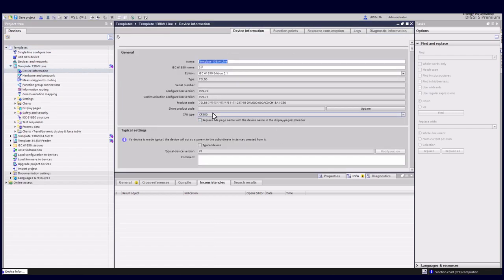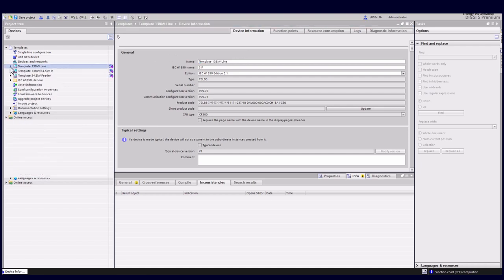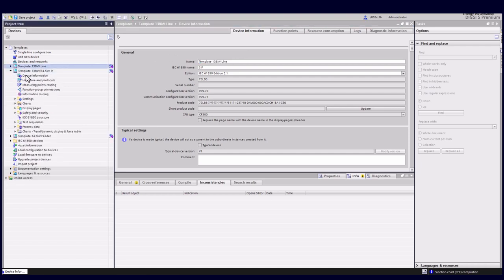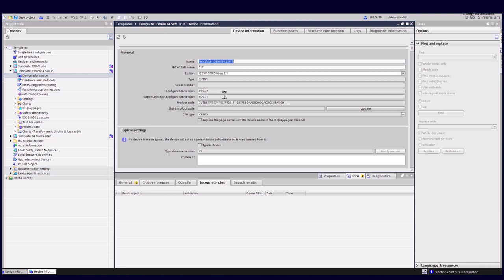Let's kick things off by starting with a solid base in DIGSI 5. We've got a preset lineup featuring a SIPROTEC 7SL85 device geared up for protection and control schemes on a 138 kV line. Plus, there's a transformer set up for 138 kV to 34.5 kV operations using SIPROTEC 7UT85, and lastly, a typical device for our 34.5 kV medium voltage feeder using the SIPROTEC 7SJ85.